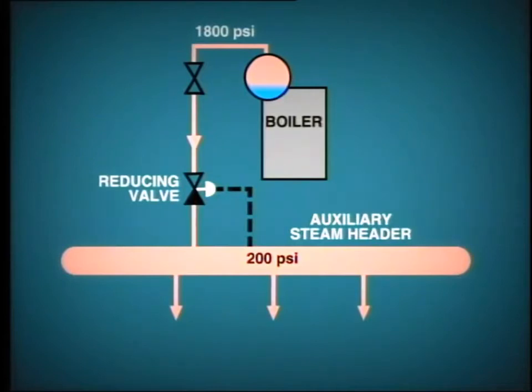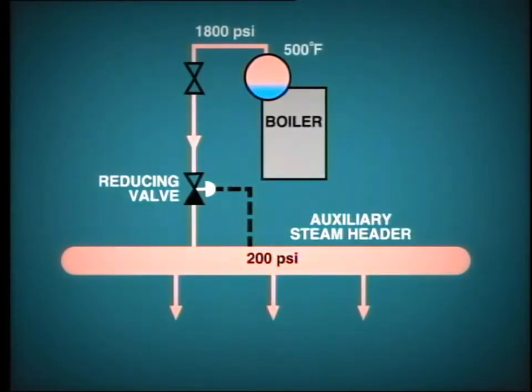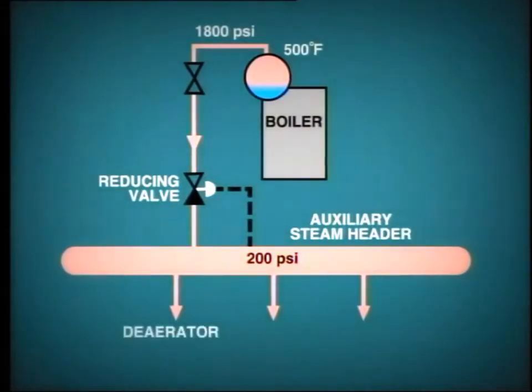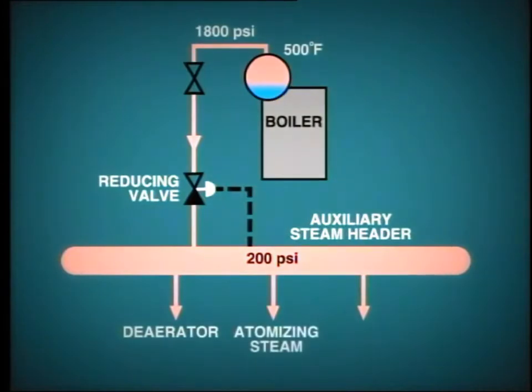Other boilers may also be selected to provide auxiliary steam to the header. The use of saturated steam from the drum is quite adequate, as its temperature of about 500 degrees Fahrenheit will provide sufficient superheat at the lower pressure. From the auxiliary steam header, steam is piped to various applications, such as de-aerator standby steam, oil burner atomizing steam, and fuel oil heating. These are just some examples; the actual steam auxiliaries will depend upon the type of installation.